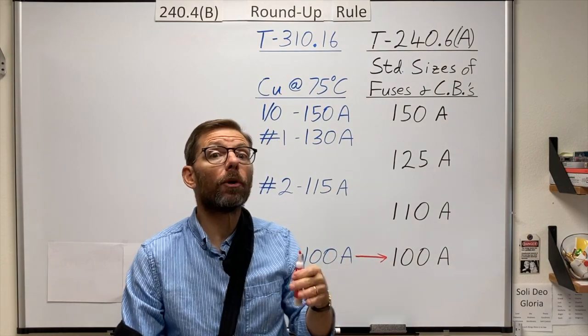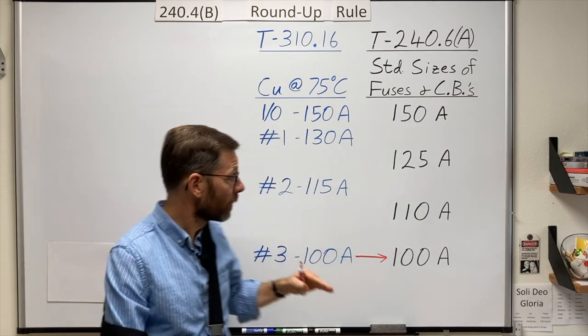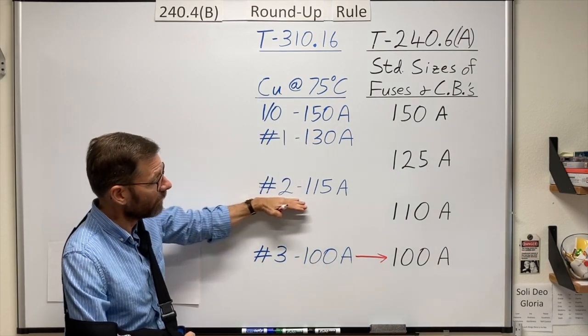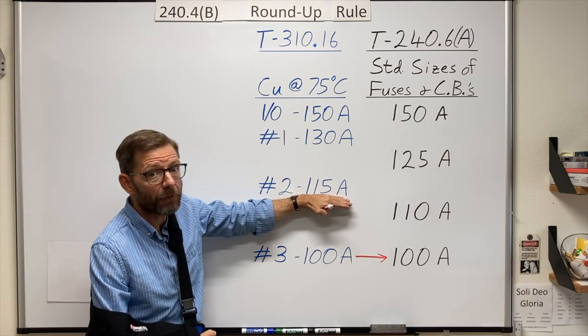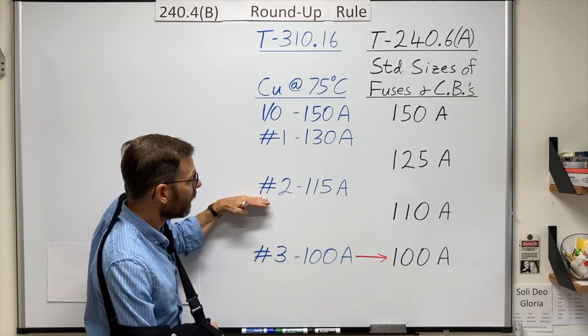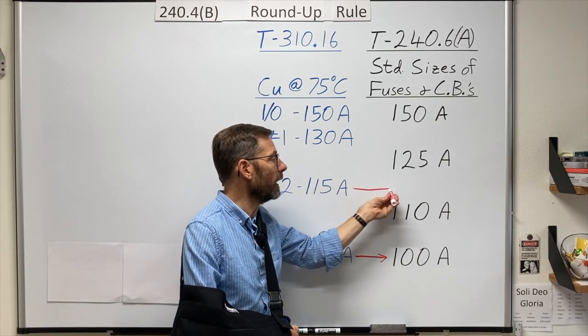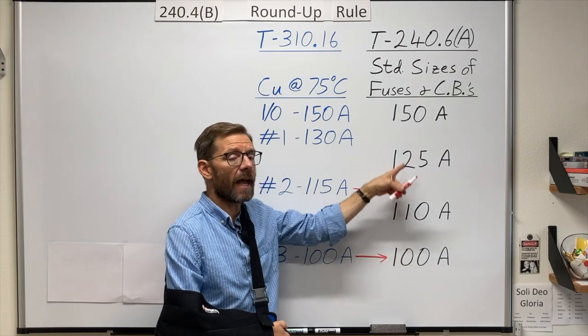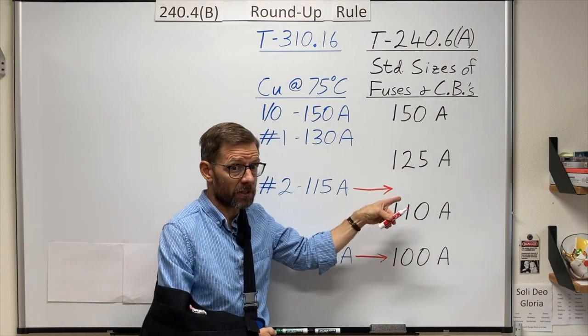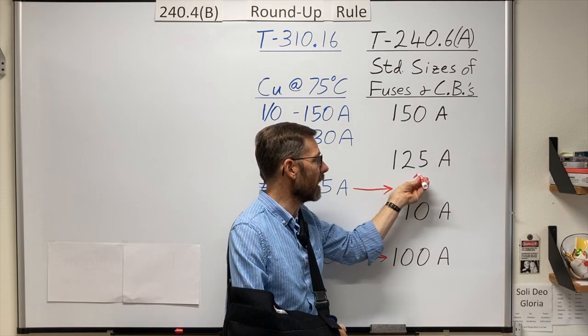However, this is a permissive rule, and it allows us, at times, to protect a conductor whose ampacity, after any derating, any adjustments or corrections, if the conductor's ampacity comes in between two standard sizes overcurrent devices, I can protect this conductor with the next bigger size.